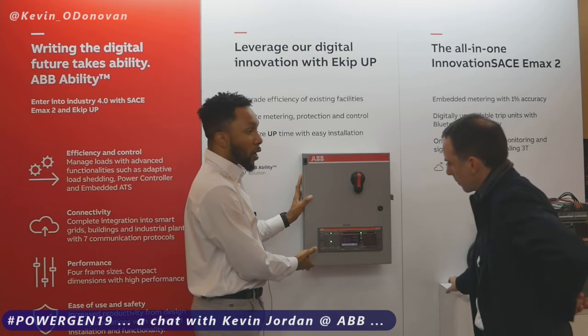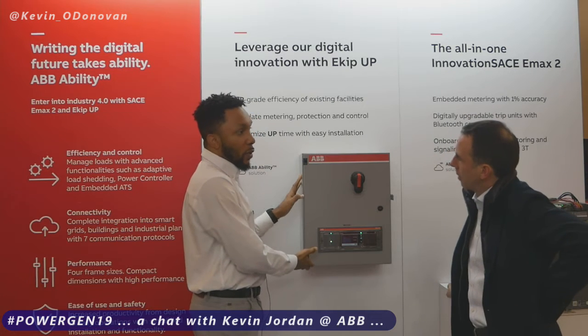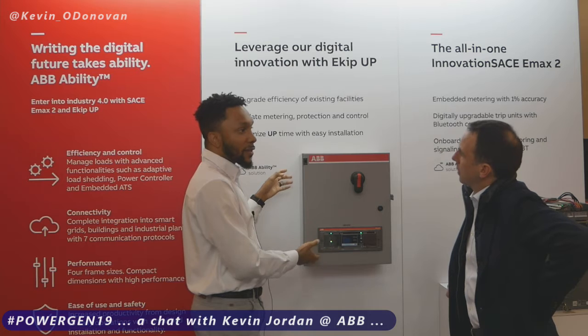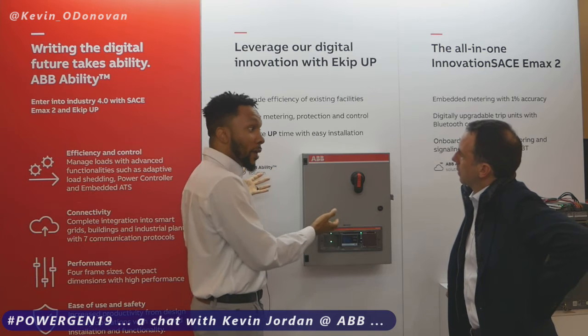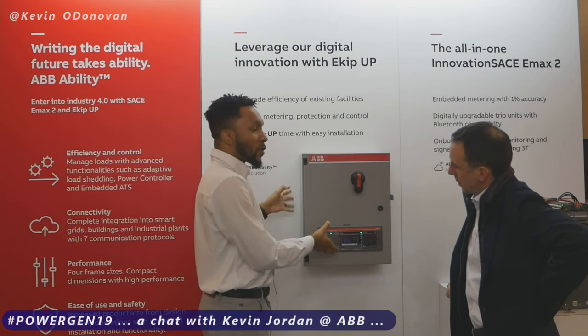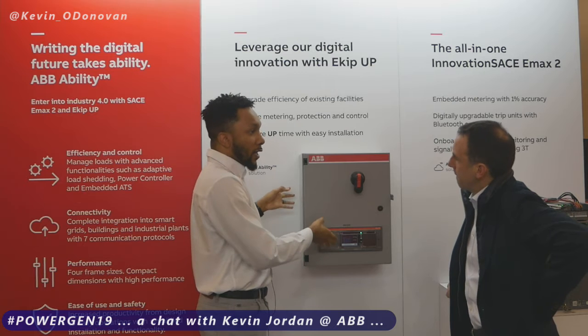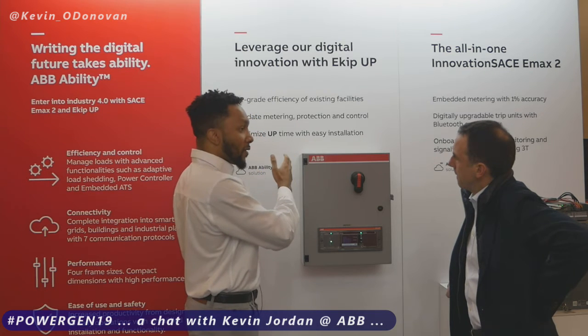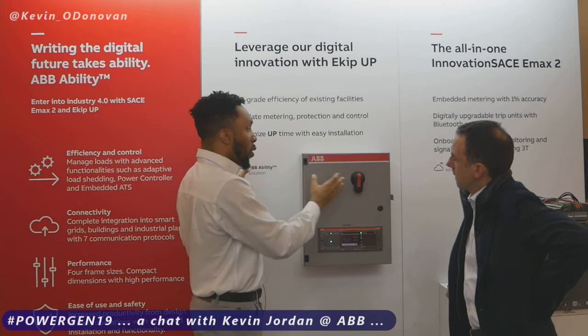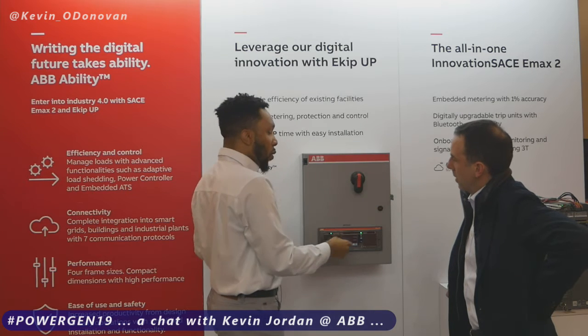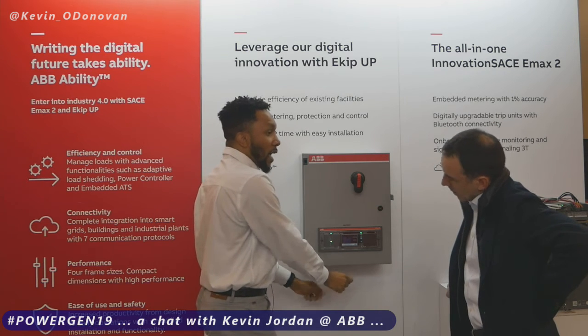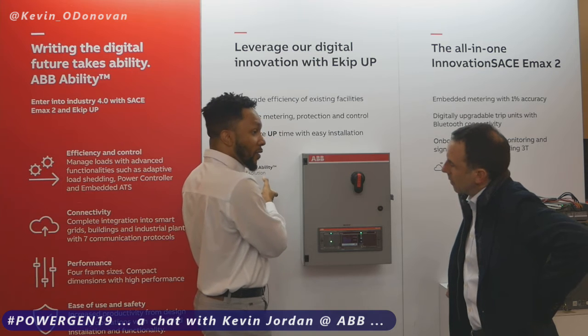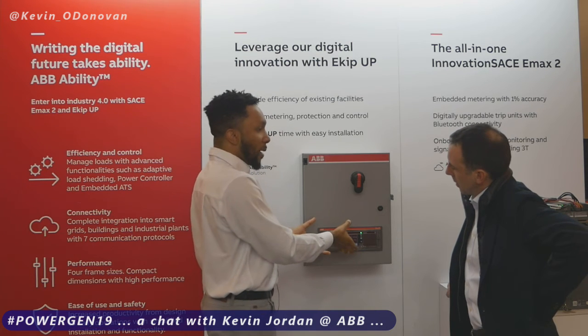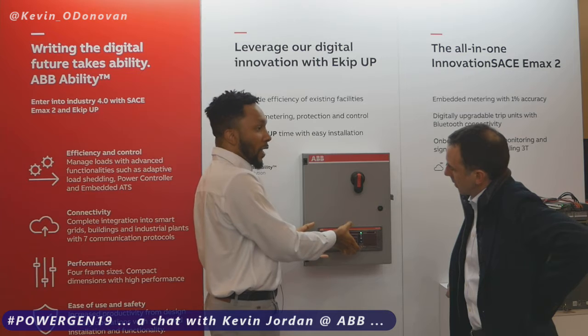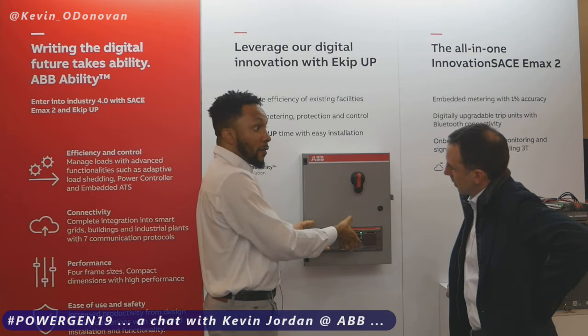This would be used in a retrofit situation, say if you already have a plant with a competitor's breaker that's not ABB. You can install this into that plant, and if there wasn't space inside the existing switchgear or switchboard, you'd install it next to it, with open core CTs connecting to the bus bar inside that switchgear. Then you have the same capability as with an existing ABB device.